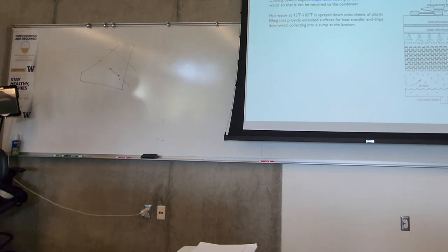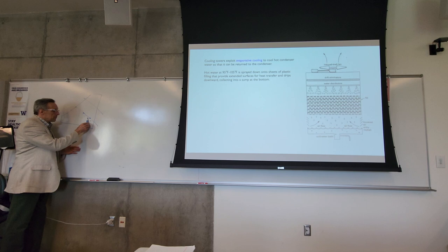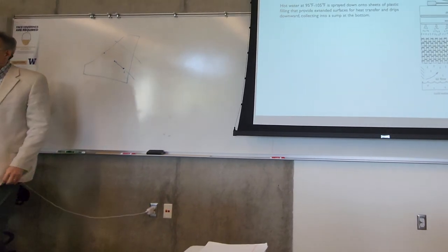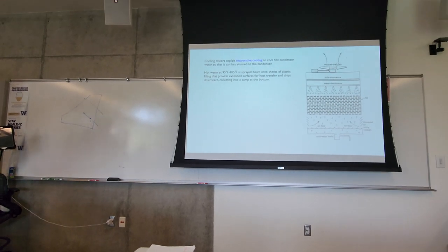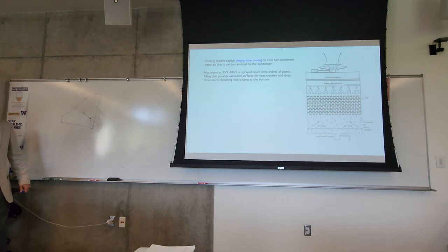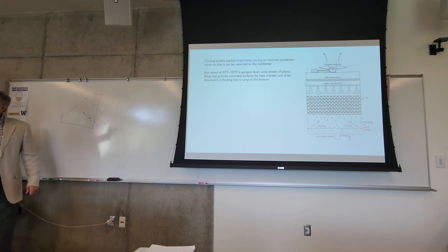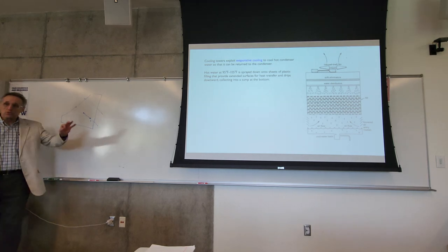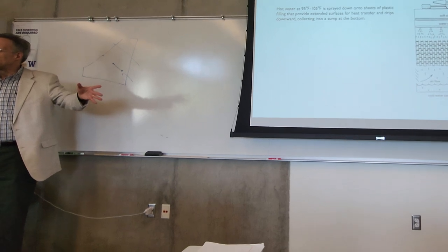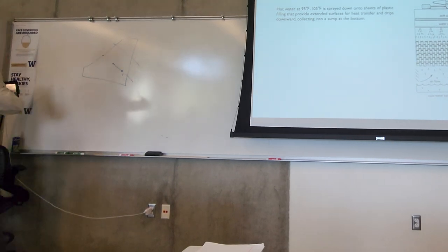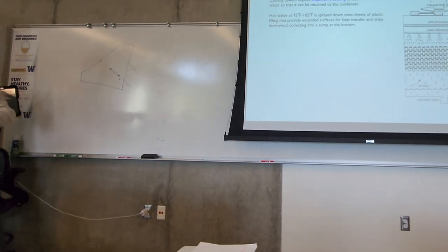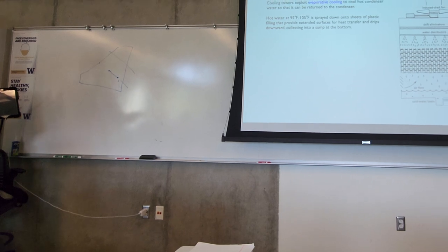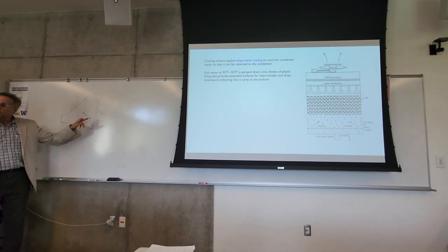And now for this to happen, the water that you're spraying has to be at the same temperature as the air. So what you do, if you have an evaporative cooler, it has a continuous circulation of water. And as that water circulates, it reaches a steady state temperature that's equal to the temperature of the space that it's working with. And in that setup, then the cooling is constant enthalpy. Now, if the water is cooler, if you're spraying cold water, then it's not going to be constant enthalpy. It's going to be a little bit different.